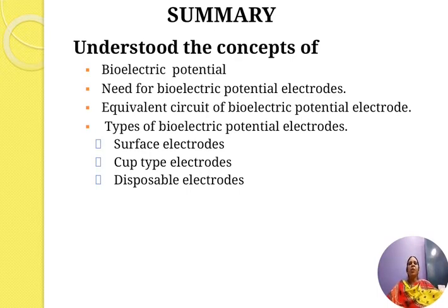Then we have disposable electrodes. Disposable medical electrodes include a disc formed of semi-rigid plastic material having a recessed embossment located centrally. A metallic electric contact is mounted on the disc centrally of the embossment and has portions located on both sides of the disc. The absorbent pad positioned in the recessed embossment has absorbed therein an electrical conductivity gel for forming an electrical contact with the patient on whom the electrode is positioned.